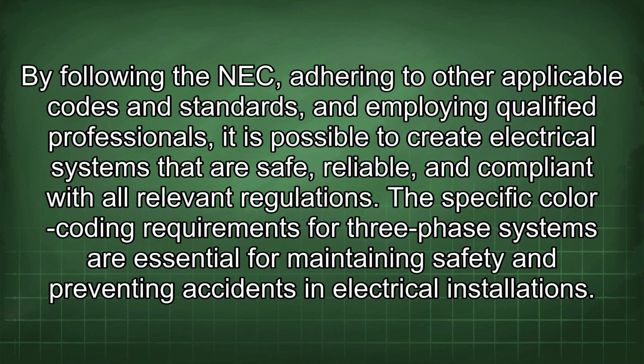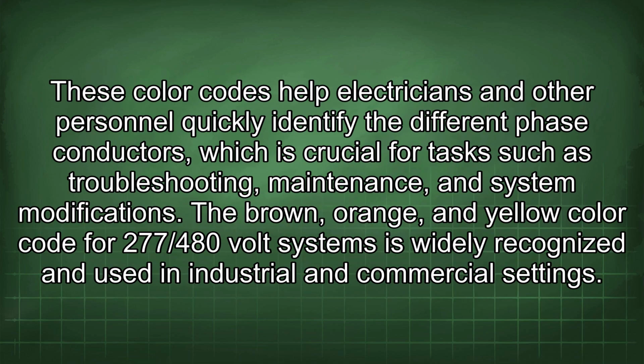The specific color coding requirements for three-phase systems are essential for maintaining safety and preventing accidents in electrical installations. These color codes help electricians and other personnel quickly identify the different phase conductors, which is crucial for tasks such as troubleshooting, maintenance, and system modifications. The brown, orange, and yellow color code for 277/480 volt systems is widely recognized and used in industrial and commercial settings.